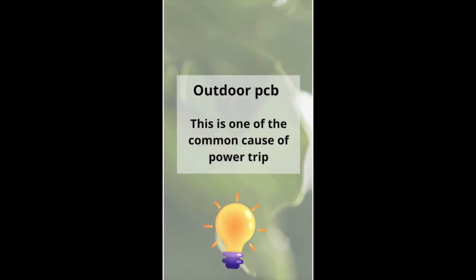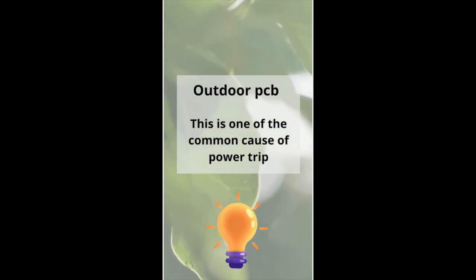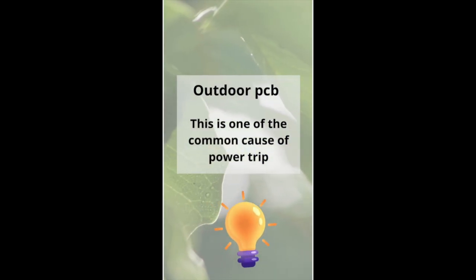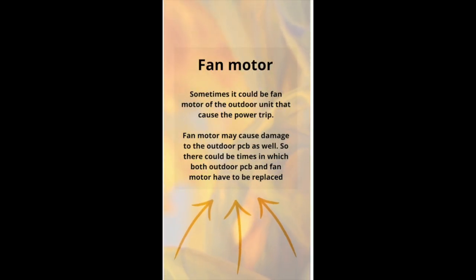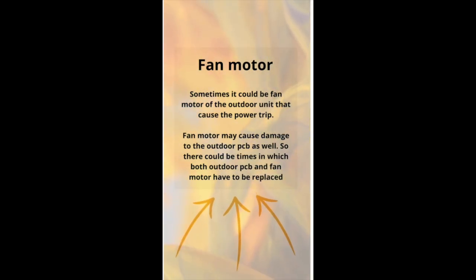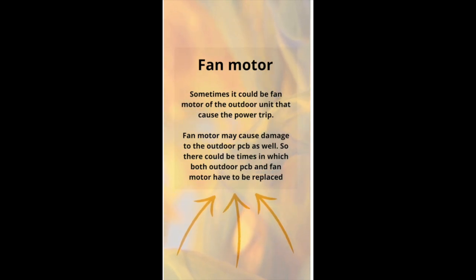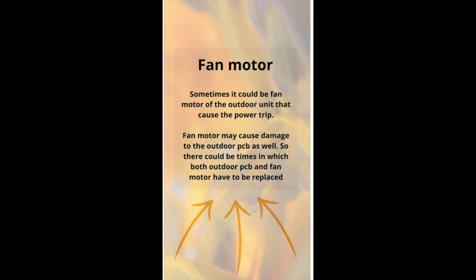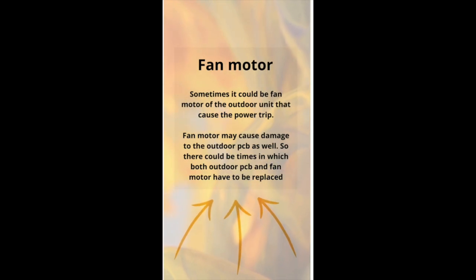An outdoor PCB is one of the common causes of power trip. Other than the outdoor PCB, sometimes it could also be the fan motor of the outdoor unit that causes power trip. Fan motor may cause damage to the outdoor PCB as well, so there could be times in which both the outdoor PCB and fan motor have to be replaced.